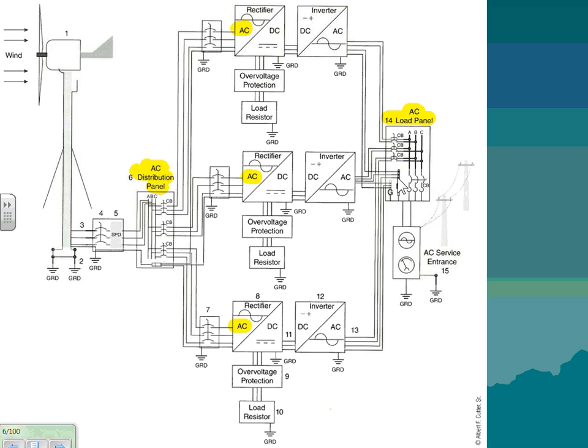Nothing changed. The only thing I want to highlight here, right in here, can you guys see the ground and the neutral? This is a non-separately derived system. The neutral of the grid and the neutral of your inverted signal from the wind are bolted together. So that's really just an illustration of all the numbers if you have to have a three-phase system. Any comments, any questions with that?